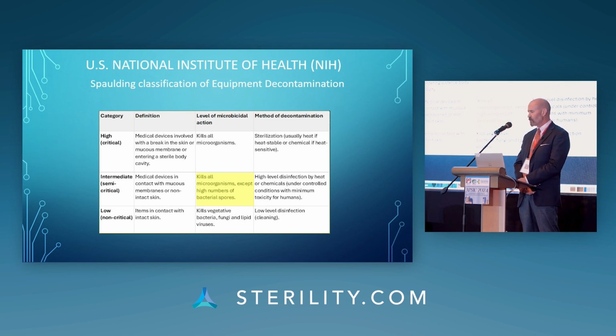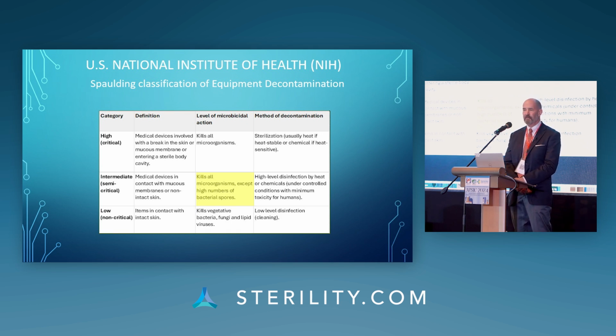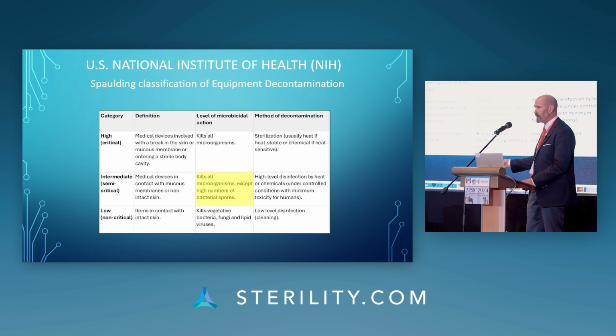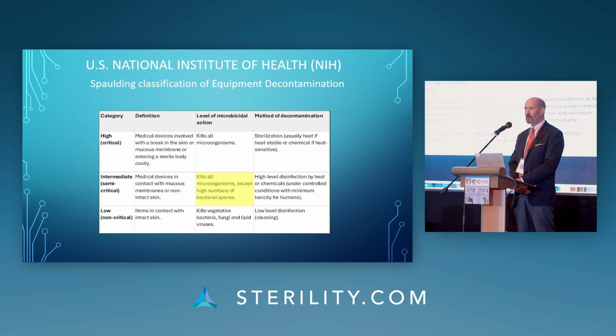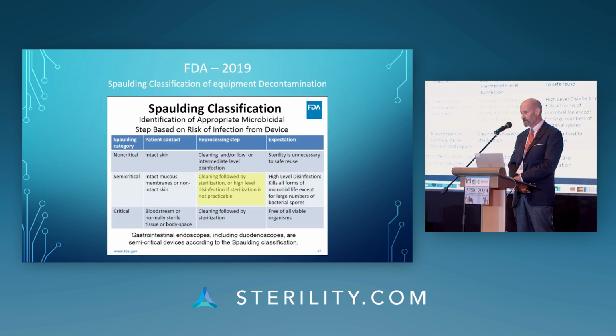This is a quick chart of the Spaulding classification system. I want to draw your attention to the area that's highlighted. This is the reprocessing of semi-critical devices. And for decades, the recommendation has been that high-level disinfection is adequate for semi-critical devices. And this has been okay for really the 50 years or so that Spaulding has been in effect. However, recently this has changed.